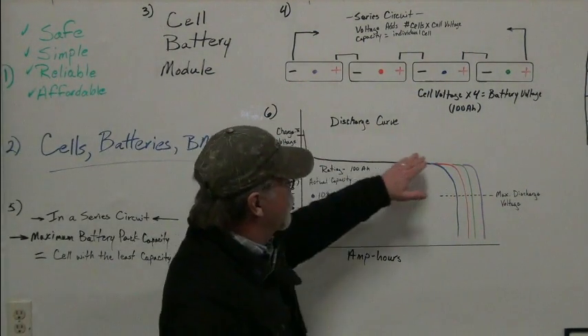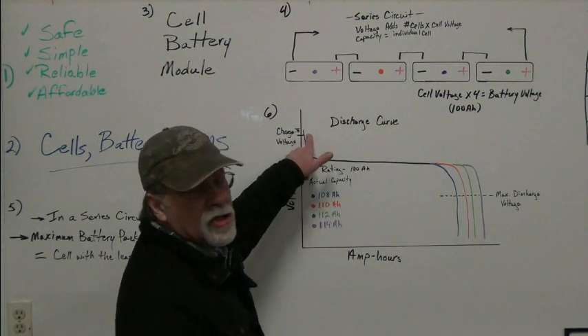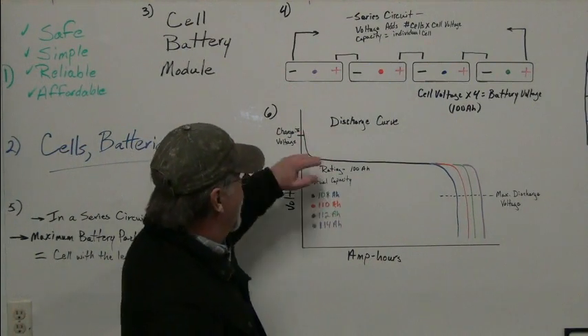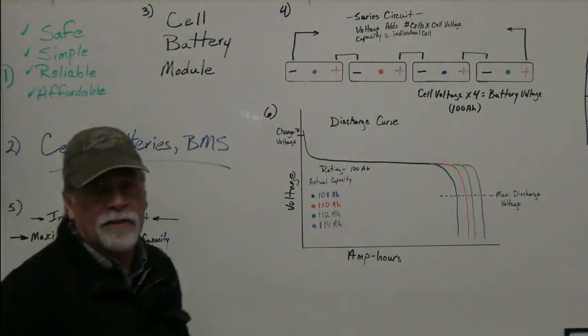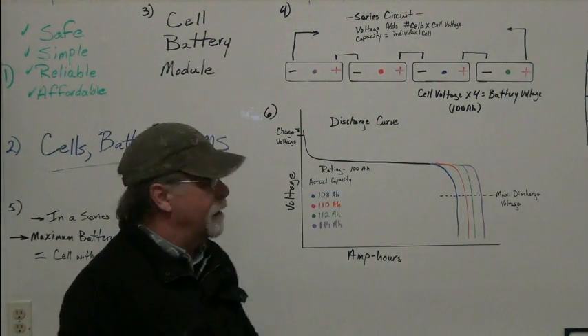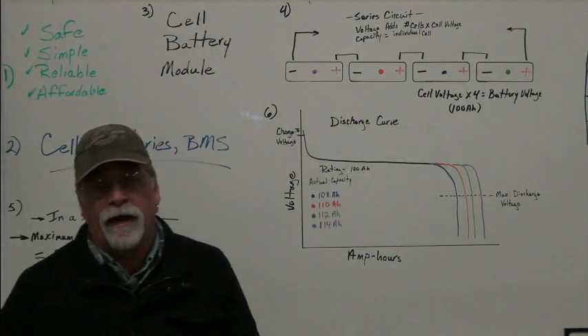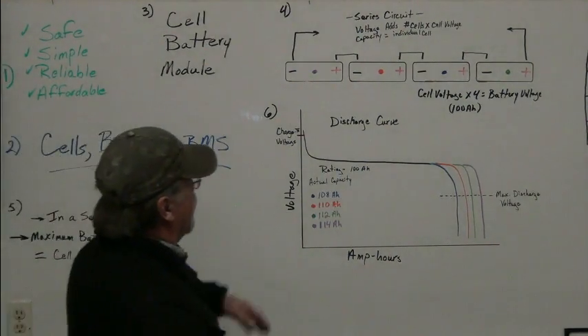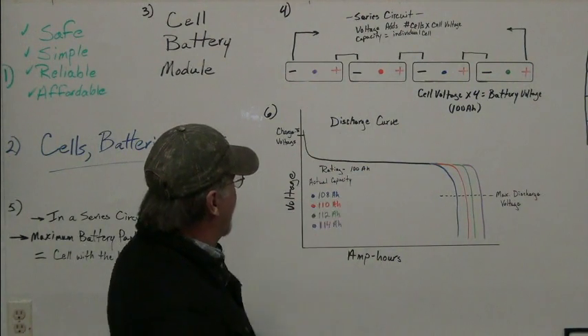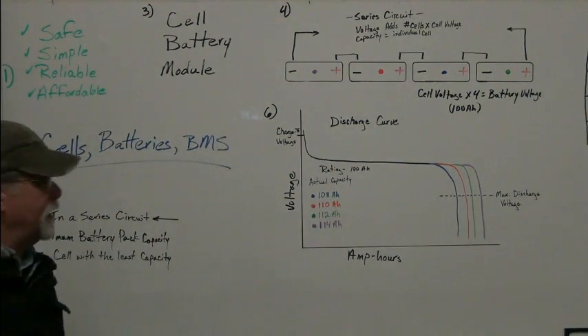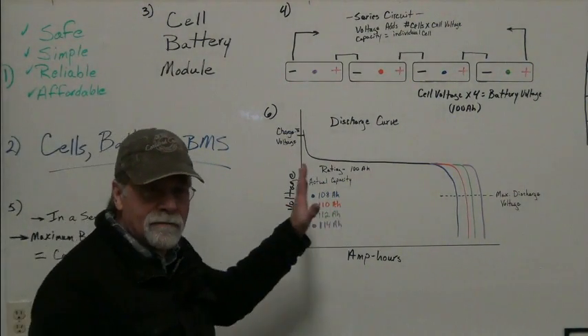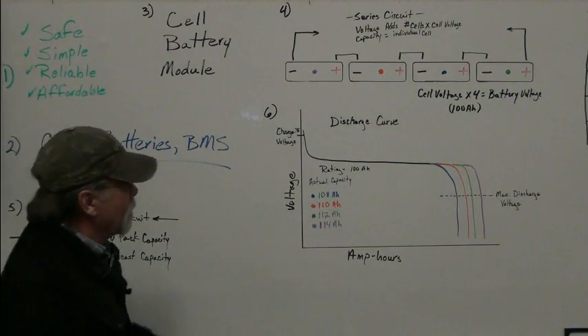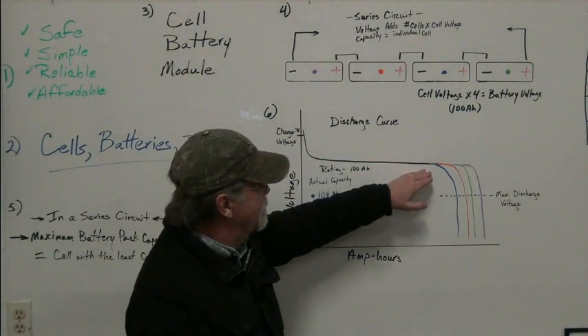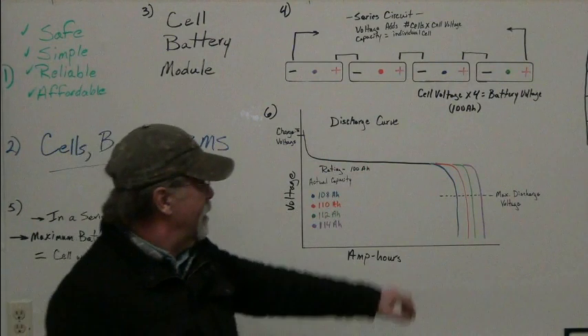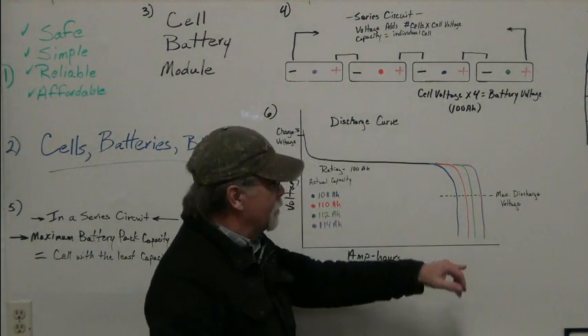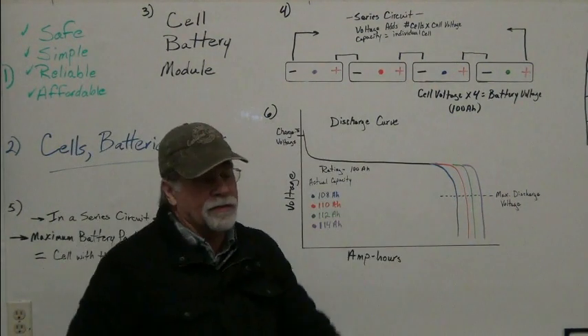In this example we're showing the discharge curve. We're starting at our charge voltage, and it's going to drop down to this line here, which is your nominal voltage. You can see the nominal voltage is fairly flat, and then you get out to this knee, and it drops off pretty quick after that. In this example we're showing 4 cells, and one of them's got 108 amp hours, then 110, 112, 114 — this is just a hypothetical teaching example. So as they're discharging, the one with the least capacity is going to go over that knee first and head down towards its minimum voltage.